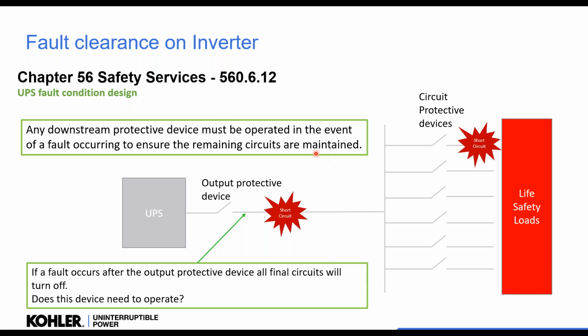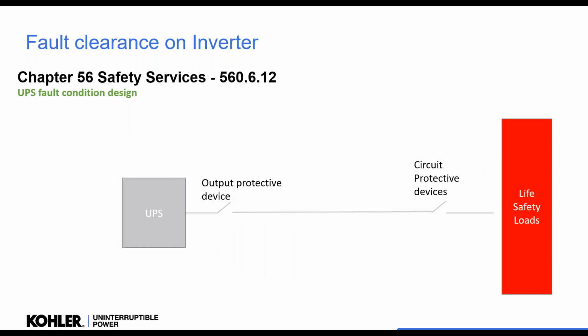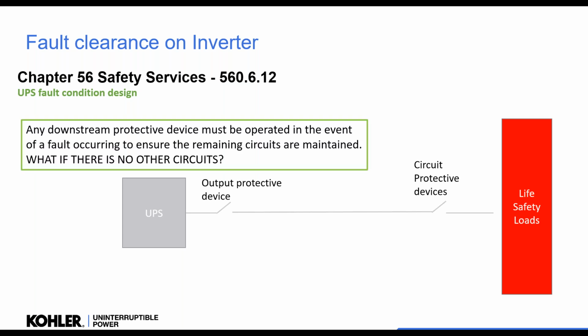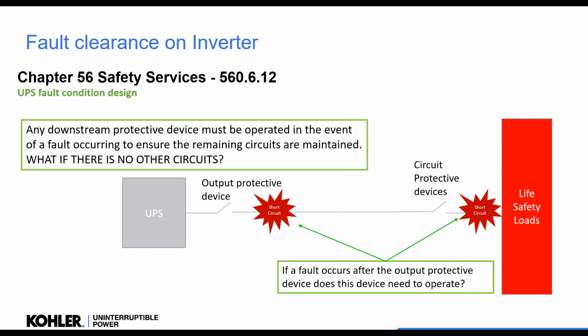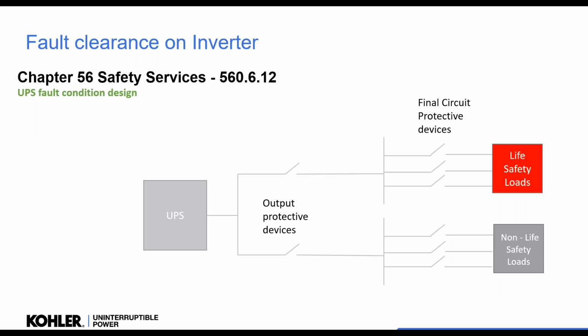Okay. If we do have a fault here, it does say that any downstream output protective device should be able to clear it. But if we lose that one, we're going to lose all of it. So does it really need to trip this device if we have a fault here, or can the UPS just turn off? Alternatively, does this actually need to be a protective device? When we have one circuit here, if there is no other circuit connected, and we have a fault anywhere, does it need to operate, or can we just turn the UPS off? This is where some of the regulations are pointing towards having one UPS per load for life safety. So if there's a problem downstream, the UPS just turns off and makes things safe. Now, of course, if we use a UPS centrally, we've got several boards on it, and some people do want to put non-life safety systems on them.